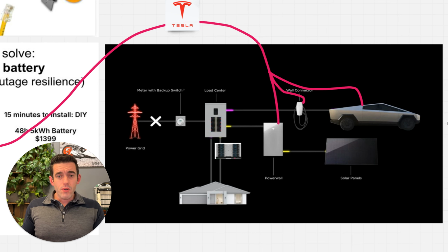But when you have a utility outage from Rocky Mountain Power, it takes between half a second and about 2 seconds for the power system to recognize, hey, power's not there, disconnect the house from the utility, and then allow that Cybertruck to start providing power to the house. Well, all of your IT systems went off within the first 20 milliseconds. Blink of an eye.